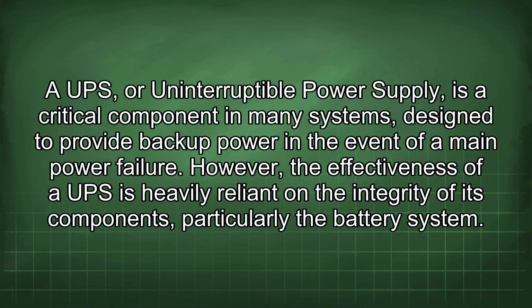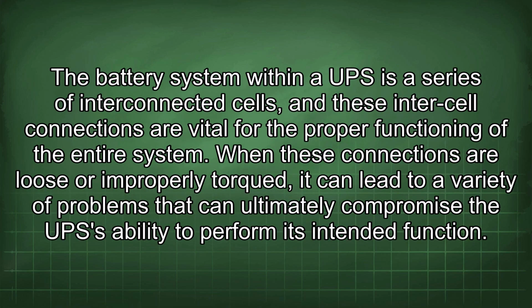UPS, or uninterruptible power supply, is a critical component in many systems, designed to provide backup power in the event of a main power failure. However, the effectiveness of a UPS is heavily reliant on the integrity of its components, particularly the battery system. The battery system within a UPS is a series of interconnected cells, and these inter-cell connections are vital for the proper functioning of the entire system. When these connections are loose or improperly torqued, it can lead to a variety of problems that can ultimately compromise the UPS ability to perform its intended function.